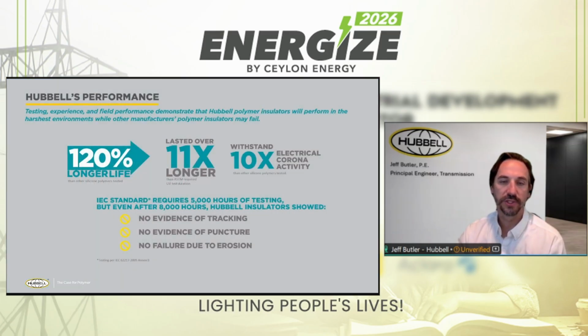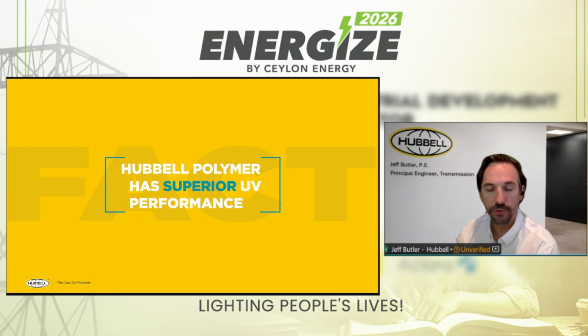Now let's talk a little bit more specifically about Hubbell. So Hubbell, we took our polymer, we use our own proprietary silicone rubber polymer, as well as the ESP, the enhanced silicone polymer. Those are Hubbell recipes. They're controlled. Nobody else and no other manufacturers use those. So we took those and we compared them to other manufacturers, other materials that were available in the industry. And we learned where our rubber performed compared to other rubbers, other polymers, other composites that were available in the industry. And one of those things we learned was that we had superior UV performance.